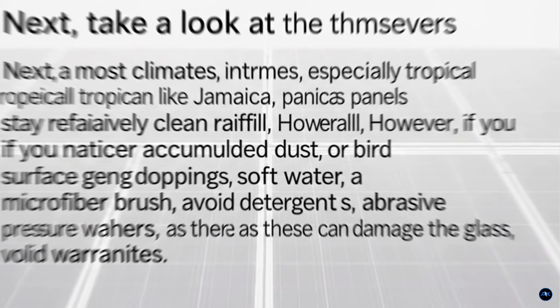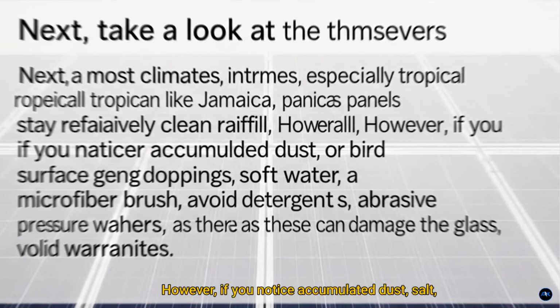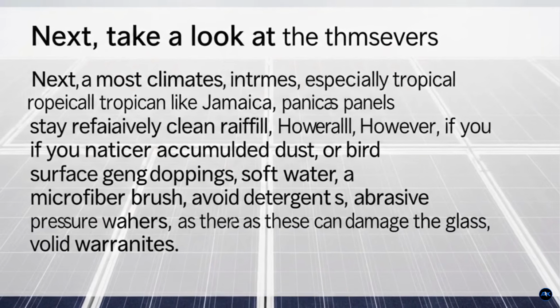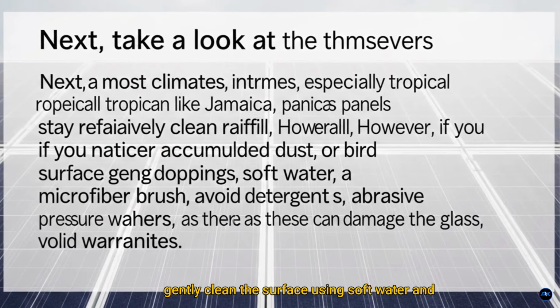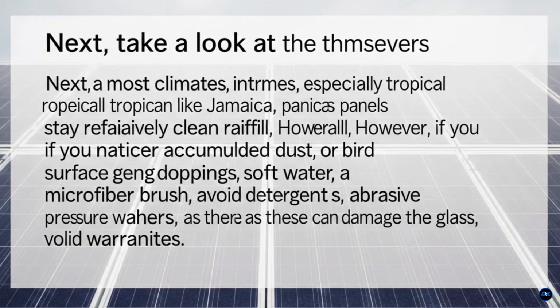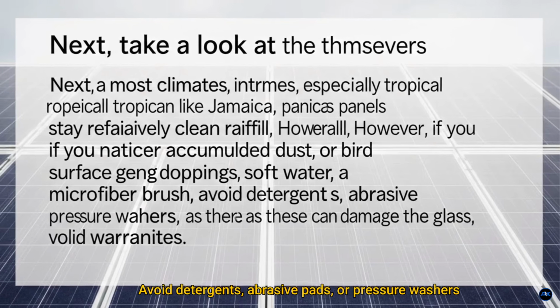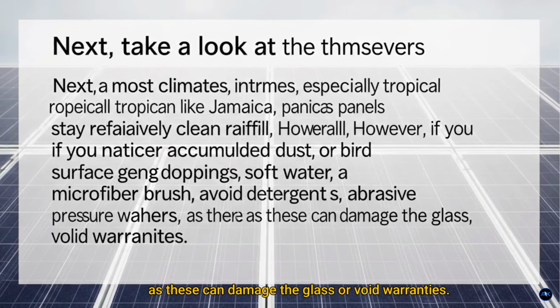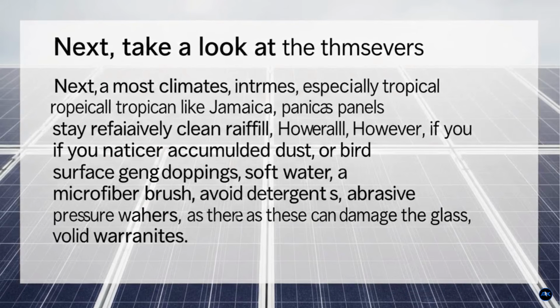Next, take a look at the panels themselves. In most climates, especially tropical regions like Jamaica, panels stay relatively clean thanks to rainfall. However, if you notice accumulated dust, salt, or bird droppings, gently clean the surface using soft water and a microfiber brush. Avoid detergents, abrasive pads, or pressure washers, as these can damage the glass or void warranties.